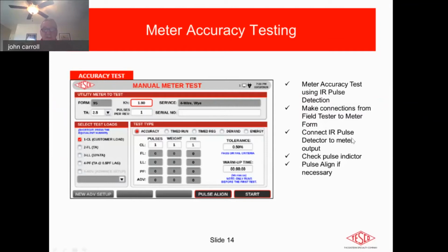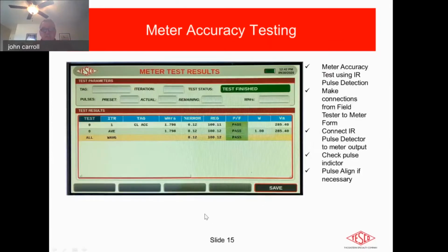Connect everything up, connect the pulses, check them if necessary, and hit the start button. When we hit the start button, we run a test. When the test is complete, which takes a very short time, with one pulse with a meter, it could be less than 20 seconds or so. It just depends on how fast, let's say, the meter is rotating around when it gets its pulses. And what we're looking at is really just the meter test results. The prime one is this first test result here, which is the classification of the tag, the customer load accuracy test.